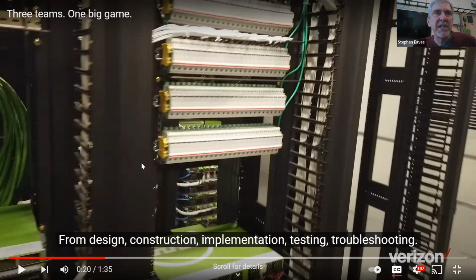But in this case, the data channels and power channels have been converged, going back to digital convergence. A common team with common skill sets pulls the cable, and many times the fiber and copper are in the same cable jacket. So the power goes with the fiber, up through the cable trays and out to the remote location, which might be 1,000 feet away.